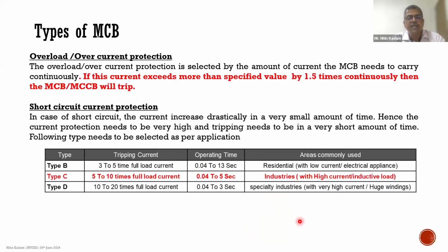In case of the MCBs, the tripping current values and operating time are also specified in case of type B, type C, and type D. For elevator application, generally we are using the type C, which has 5 to 10 times the full load current value, and operating time is 0.04 to 5 seconds. And in case of escalators, type D is used, where you have the tripping current values of 10 to 20 times the full load current, and 0.04 to 3 seconds is operating time.